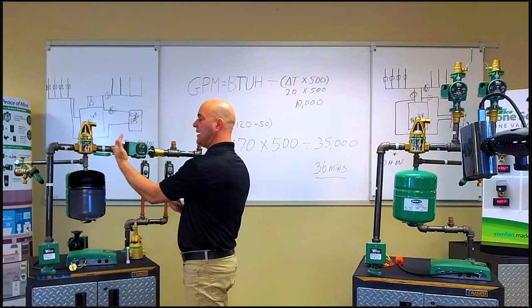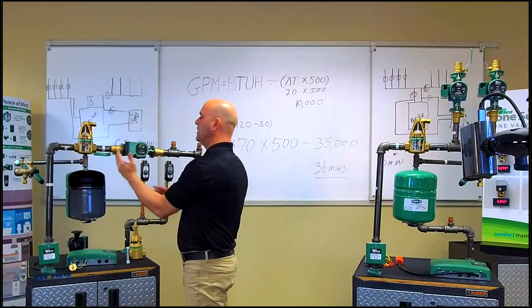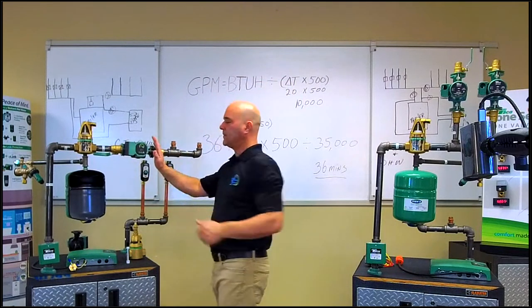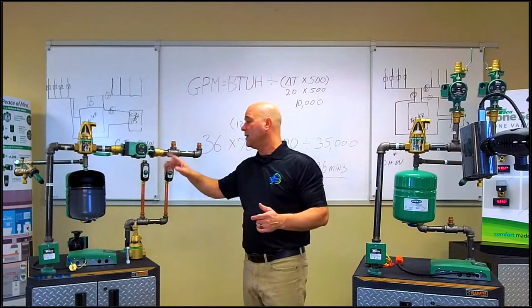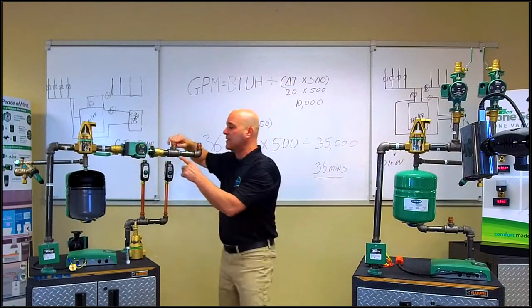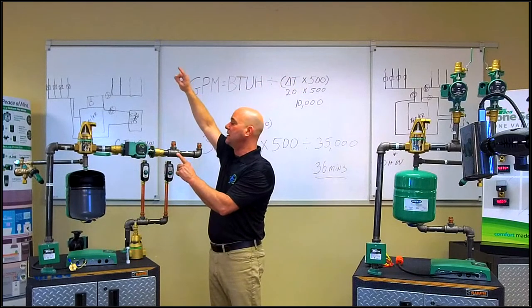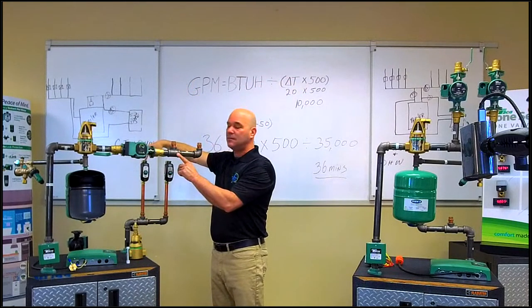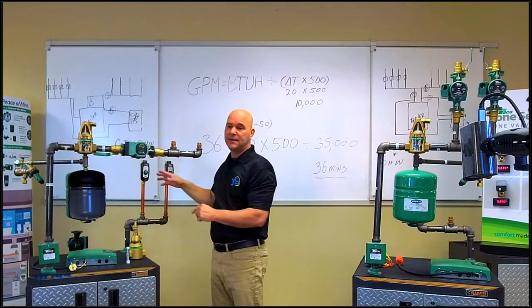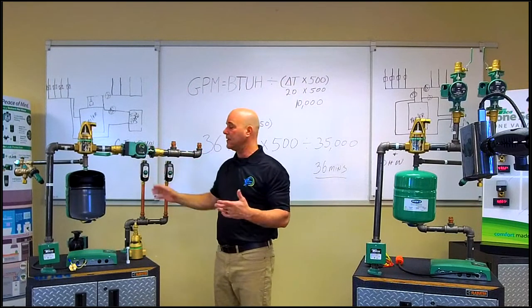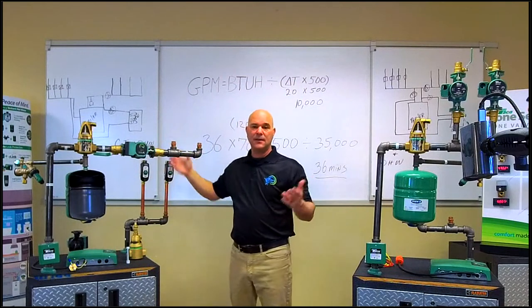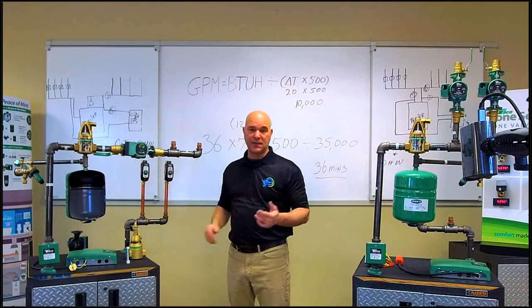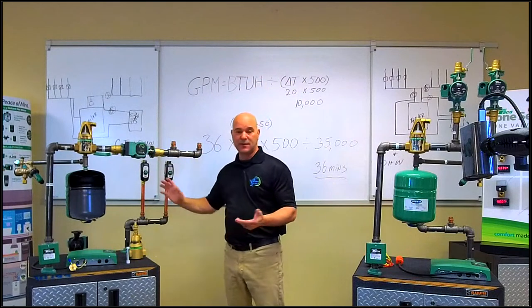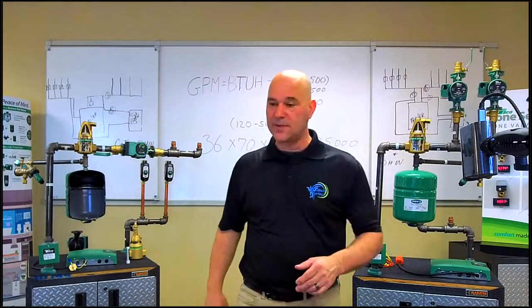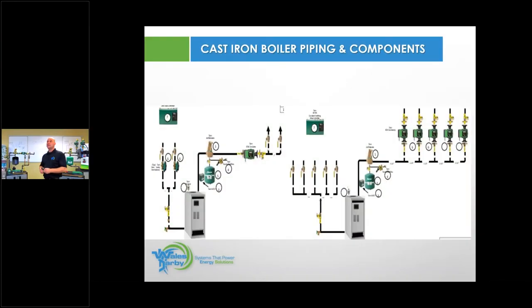Our goal is to keep the backside at the system pressure, which is 12. And when this comes on, we want to be able to bump that up. It'll bump it up 4 to 5 PSI. And then we're going to use that additional 4 to 5 PSI to send it up through the heat circuit, out through the heat emitters, back down to the return side. On this one, we have the zone valves on the return. The zone valves could be on the supply. It's really a preference thing. I like them on the return just because it's a couple degrees cooler and maybe they're going to live a more comfortable life and give you better performance. But that is a typical cast iron type boiler pipe job.